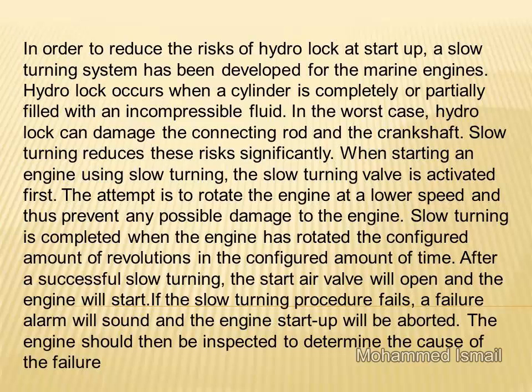If the slow turning procedure fails, a failure alarm will sound and the engine startup will be aborted. The engine should then be inspected to determine the cause of the failure.